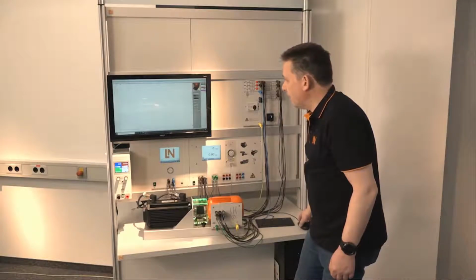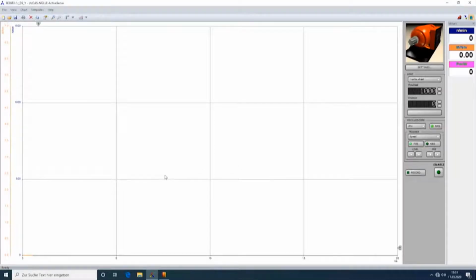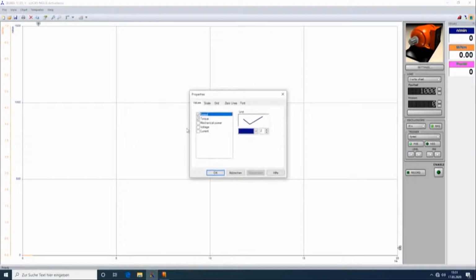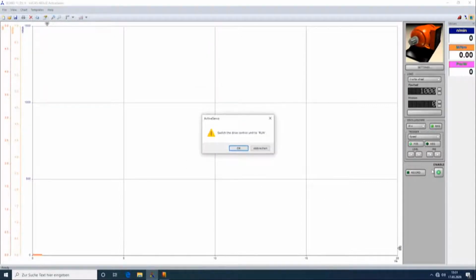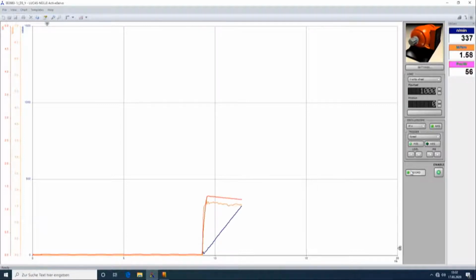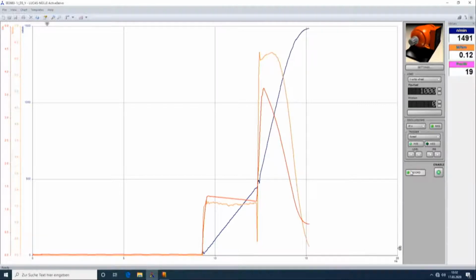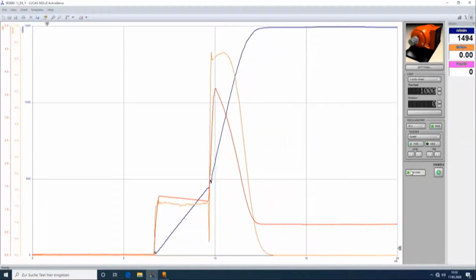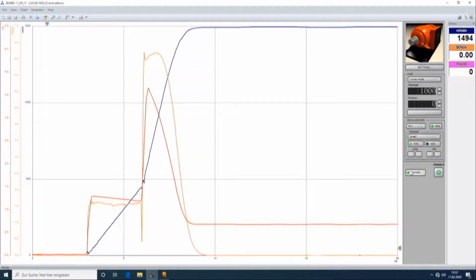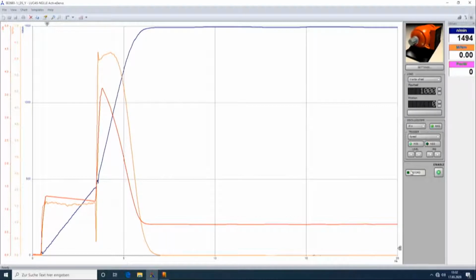So now I have adjusted the flywheel with the values. But for the inrush current, it's also interesting to see the current. With a double click, I can adjust the current here. Start enable again and press the record button. All the values are now measured, and in the next step I start the motor. If I start the motor in Y and then switch to delta, I can see the behavior directly. We start with a small current, then a higher current when I switch to delta. And we also see the torque given by the speed up of the system.